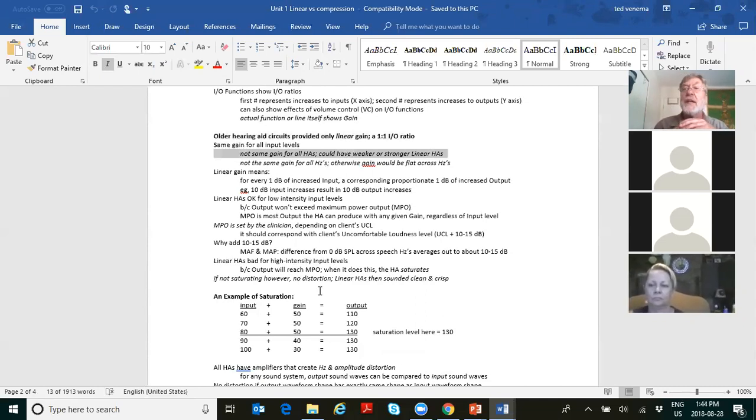And we said last week, you could visually tell wearers of linear gain hearing aids because they were constantly changing the volume controls on their hearing aids. If the gain was set right for average conversational inputs like speech, like 65 dB SPL, average, my father can beat your father at checkers, yakety yak, then that gain might be great for average, but for a whisper, it wasn't enough. And so the guy had to crank it up. And then for loud inputs, suddenly it went into peak clipping and it sounded horrible. So the guy was turning it down.